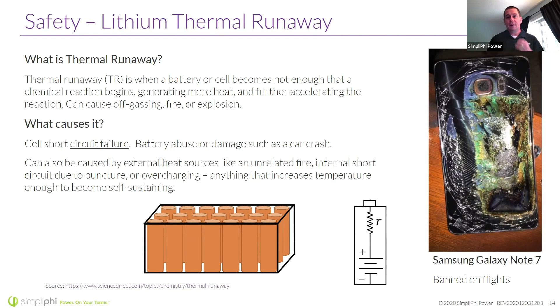It could be overcharging. You've got to be really careful with your set points on batteries, because if you overcharge them, you can have thermal runaway. In fact, a lead acid battery can also have thermal runaway. If you continue to charge it, overcharge it, the resistance becomes less, the battery takes more and more, and now you've got a thermal event mixed with an acid-based electrolyte, all bad. So thermal runaway is definitely something the industry needs to keep an eye on, because like Samsung learned with that phone, it is not looked upon favorably.